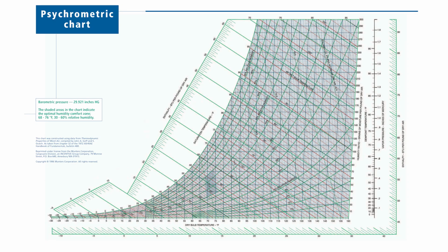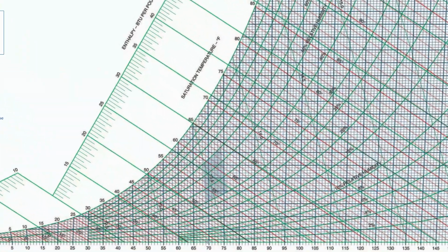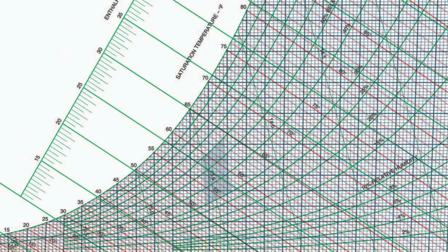Makes sense. What are some of the sanity checks an engineer can use to ensure that the moisture to air ratio is appropriate? And I guess, are there any tools that help simplify that process? So going back to figuring out how much moisture you need initially, I said you had to understand what moisture you're starting with, what moisture you're ending with, and your air volume. And then you've got to convert the CFM, for example, into mass. Well, that sometimes seems complicated. You can look at a psychrometric chart, and if you've ever looked at one, there's a lot of lines. It's very busy.